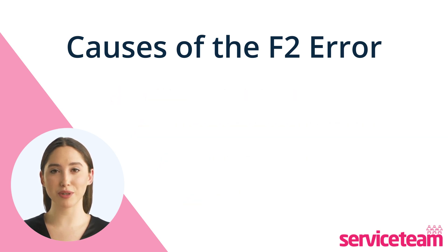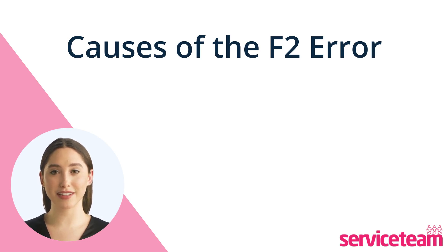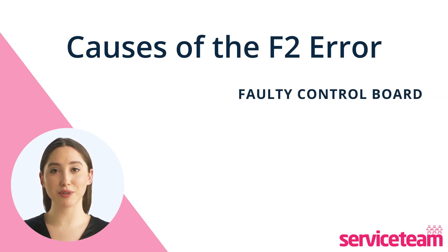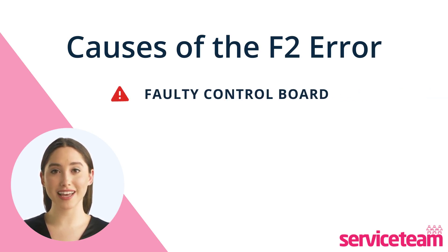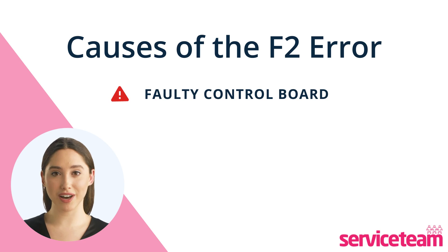The control board manages the boiler's operations by getting information from sensors and sending signals. If the control board is faulty, it can cause wrong sensor readings or fail to send the right signals to the ignition electrode, resulting in the F2 fault code.